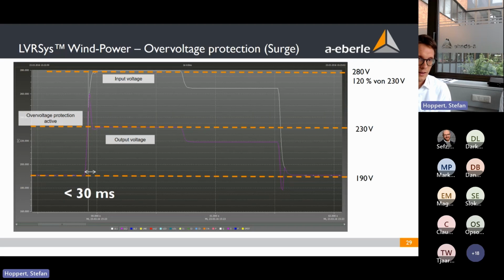And here you can see the white line, which is going up here, shows the voltage on the input side, which goes up to 120%. And the output on the pink line, purple line, shows you the output, which is regulated through the LVRSys. And within 30 milliseconds, we can regulate the voltage down by more or less 20%. So the voltage goes up, our system regulates it down and therefore protects all the devices of their own supply. This is quite a special design for this company, but it shows you that it's also possible to have it as an additional overvoltage protection with short-term reaction times.